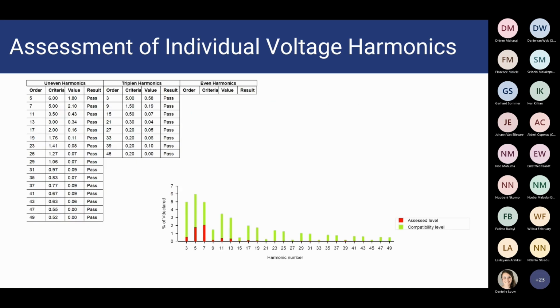Okay, here's an example of an assessment of the individual voltage harmonics. We have the table that compares, for a certain period, this month, the assessment. We compare your specific individual harmonics, the assessed value, with the levels specified in the NRS 048, and provide you with the result. This is again all automatically generated for you using our Osprey Pro reporting functionality. It also gives you a harmonic spectrum plot that compares your assessed value, that's the red, to the limits. You can see at this site, it's all well below the limits and complying with the NRS 048 limits.